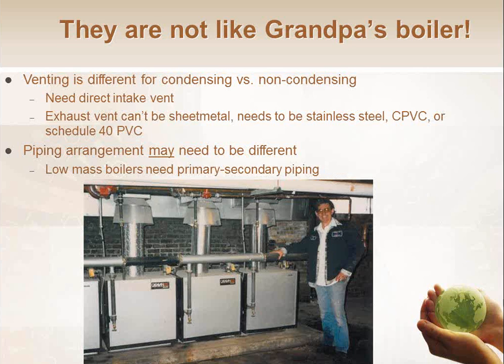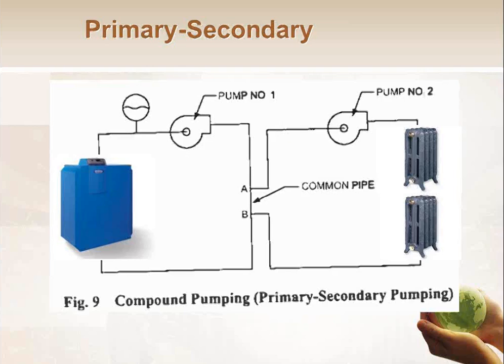When you go to a low mass boiler, it's a coil, like a wound up coil style heat exchanger. So I got to push water all the way through that coil. If I try to do that with the main pump for the whole building or the main pump for the house, it'd be a pretty big load. So we divide the workload in half, and we do half on the primary, half on the secondary. So this is what that typically looks like if you've never seen primary, secondary before.